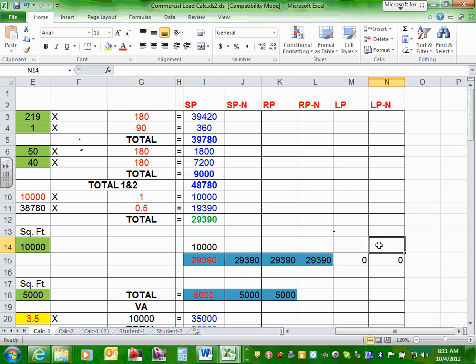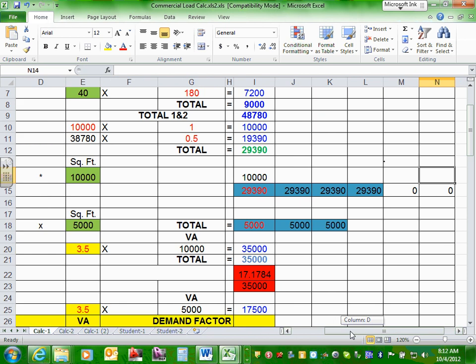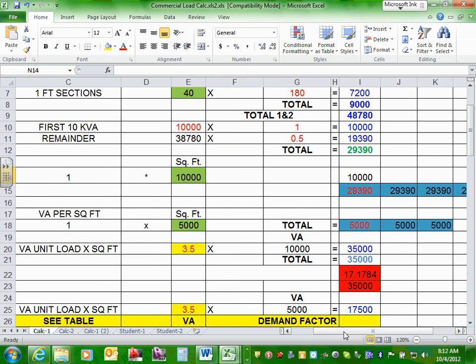Step number four: unknown receptacles. Because they're telling us we're going to add to the building 5,000 square feet, and I haven't designed it yet, I don't know how many receptacles are there. So I take 1 volt-ampere per square foot, multiply by 5,000, getting 5,000 VA. There's nothing else to compare it to since I have no actual physical receptacles yet.